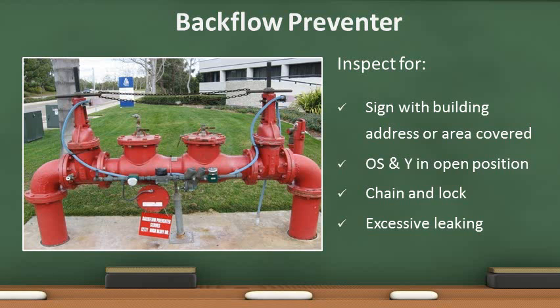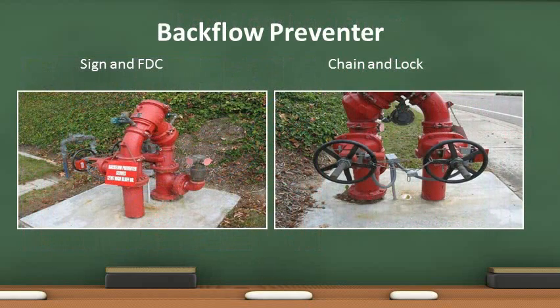Backflow preventers are equipped with fire department connections, also known as FDCs. The caps shall be in place. Remove the caps and ensure the gasket is inside. Turn the swivel and ensure it moves freely. All parts should be clean and free of corrosion and debris. Be sure to replace the caps after inspecting. The backflow preventer shall have a sign stating which addresses it serves. Note the caps are on the FDC, the chain and lock are in place, and there is no evidence of leaking or corrosion.